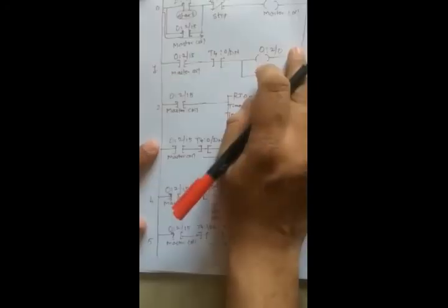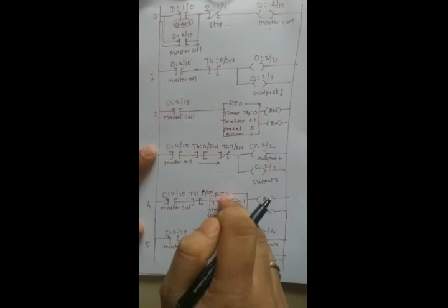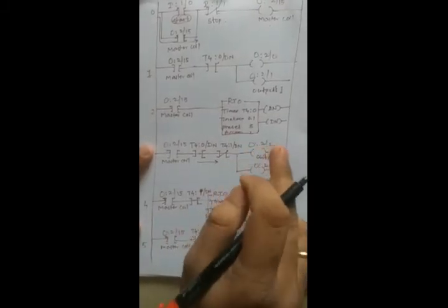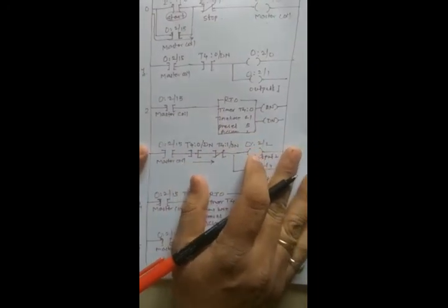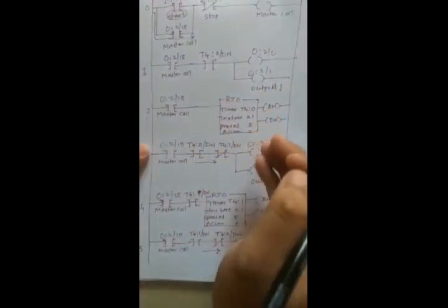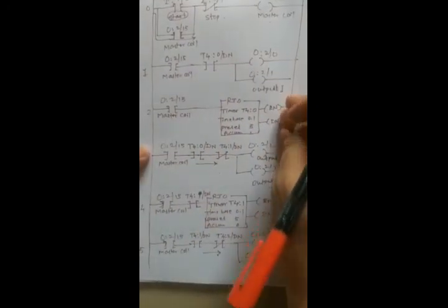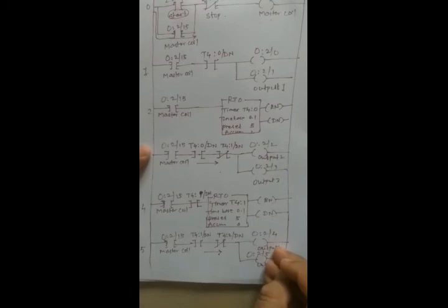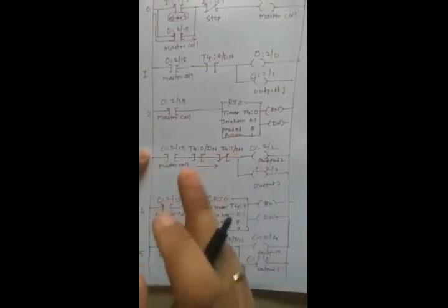Now to have a complete description of all this, the program is just a simple combination of timers and outputs, as you see. The only difference here is that we have used retentive timers instead of TON and TOFF timers. Various outputs from 0 to 5 we have used and made pairs of two outputs, like 0, 1, 2, 3, 4, 5. So one timer is provided to each pair of two outputs, and timer done bits are used to turn on and turn off the lights.